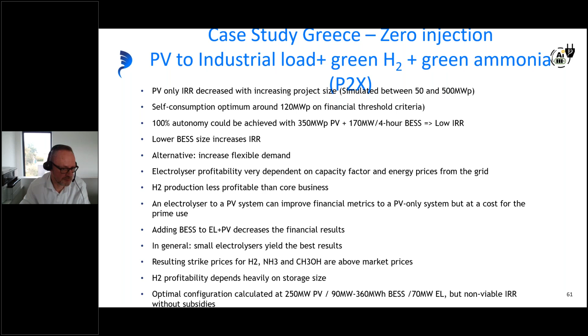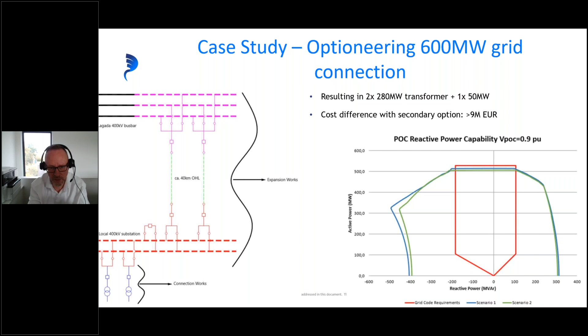Another optimization we did was for a 600 megawatt cluster of PV systems spread across a larger area, which needed to be connected to a 400 kilovolt main transport line. It resulted in a specific transformer configuration of 2 times 280 megawatt plus a 50 megawatt transformer, whereas another option considered initially would result in a cost increase of about 9 million euro. So there too you can look at how to optimize cost, what about risk, what if one transformer fails, what is the likelihood of that. All of those elements can be evaluated. This was done at a quite early stage so the developer knew how to move forward with the grid connection application and get the production license for this plant.